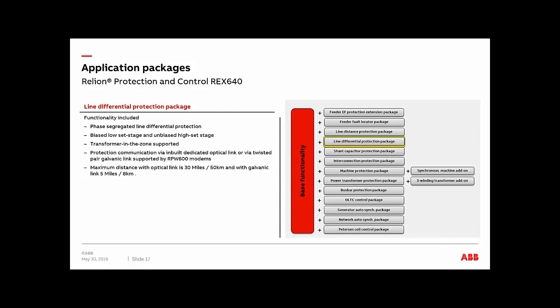It can be applied as well in a line that has a transformer in the zone of protection, and the relay can account for this through settings. We again have the possibility of transferring 16 additional binary signals between line ends at a maximum of 30 miles. This is what you would get with your line differential package. You get 5 miles if you have a galvanic link, but 30 miles with an optical link between the 2 relays. And again, the 640 has the option, like we said, of having sensors or traditional CTs for all these applications.